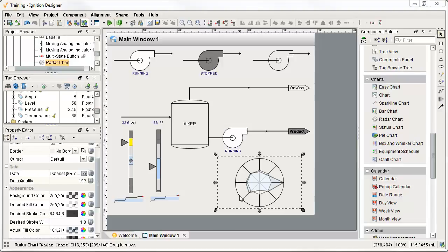This radar chart here is showing us 8 different process values as spokes with equal angles between them. As you can see, there are 2 sets of polygons that get drawn on the radar chart. The white polygon in the back is showing us the set point value for each of the process values, meaning what we want the process values to be at. Since different process values have different set points, the chart will normalize the set point so that each point is drawn in the center of the spoke, drawing a circle.